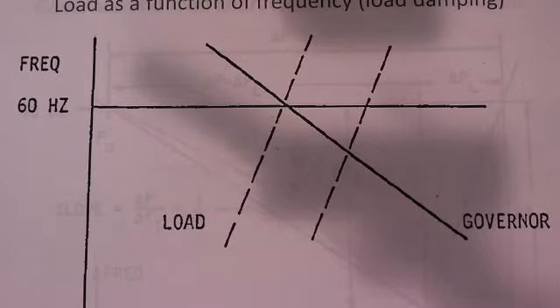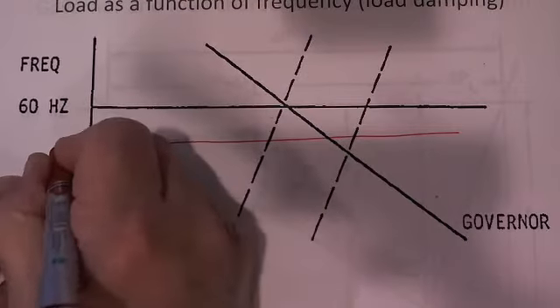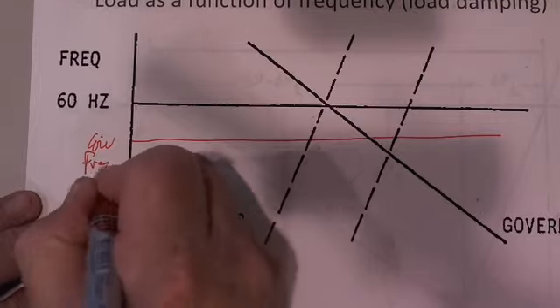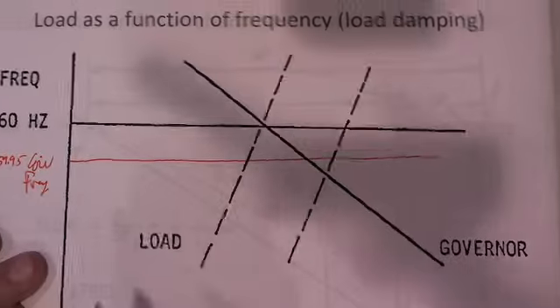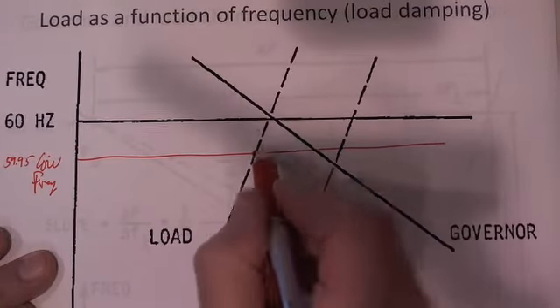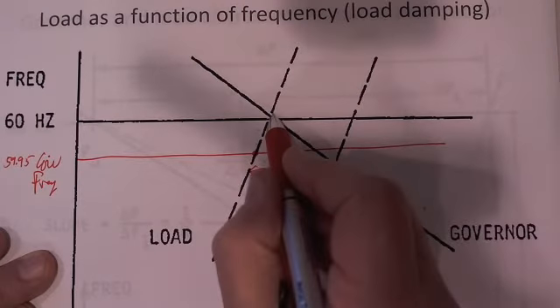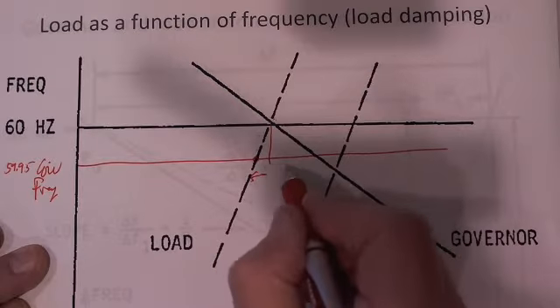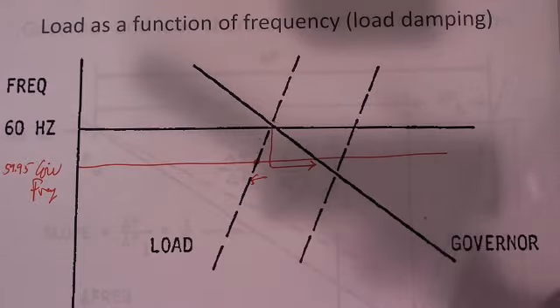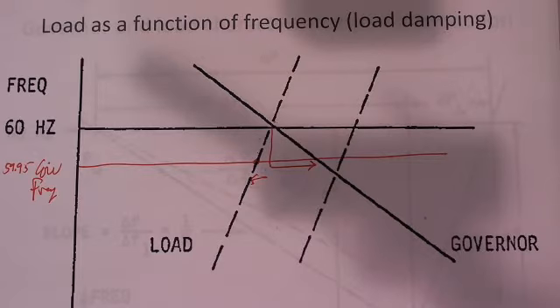So, load as a function of frequency. There is an effect on most loads where if I reduce the frequency, the load will actually go down. So for a lower frequency, I don't know, 59.95, whatever, the load, you notice, came down and it went back. Whereas for a generator, up here it came down and the generator went up. So loads have a negative characteristic due to the fact that you have motors, and the motors draw less power as the frequency changes.